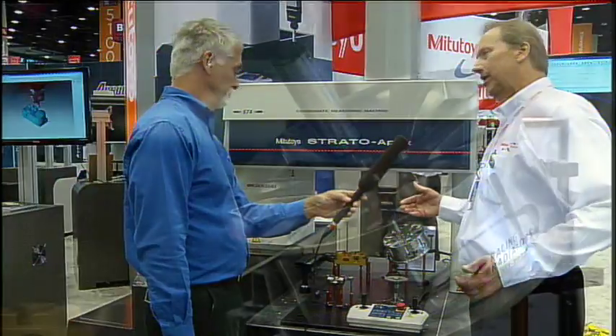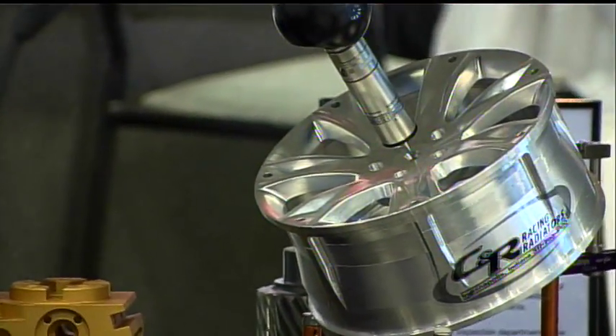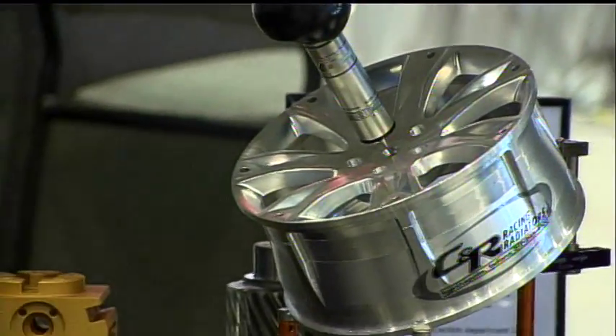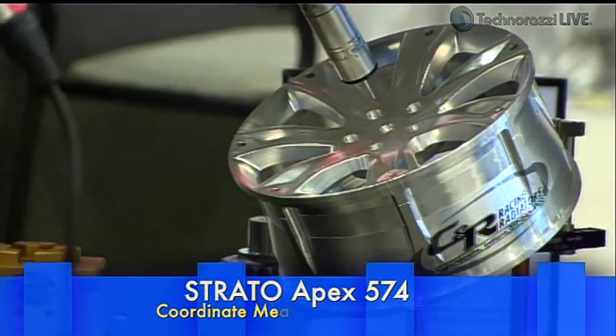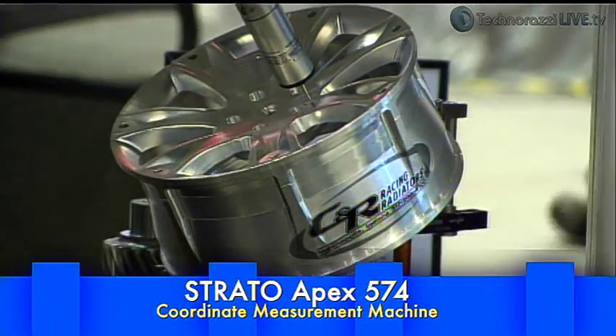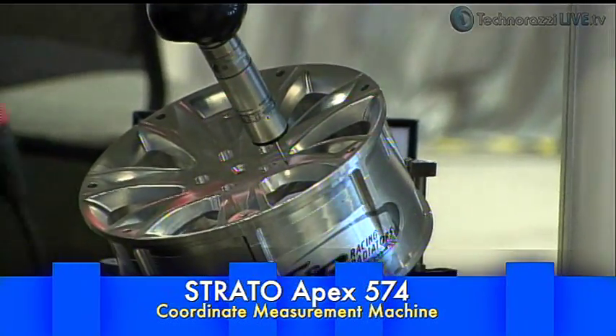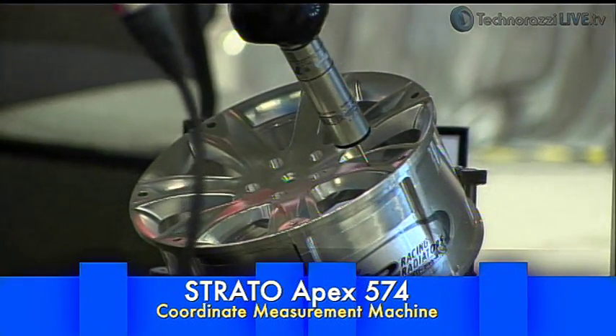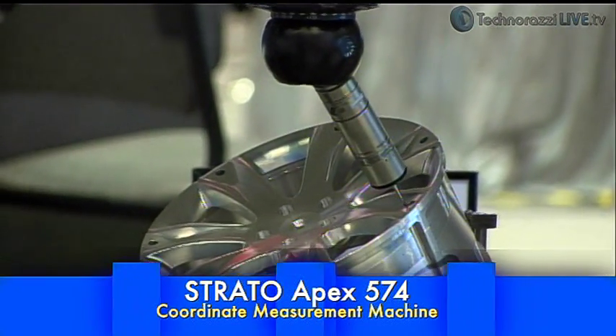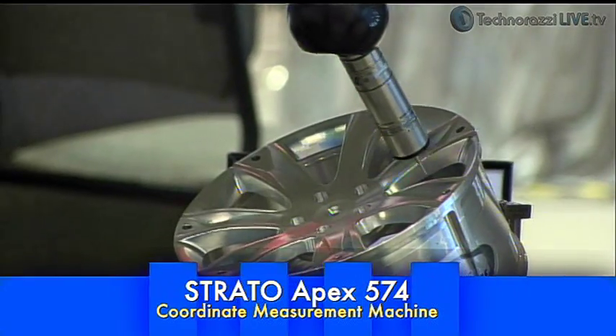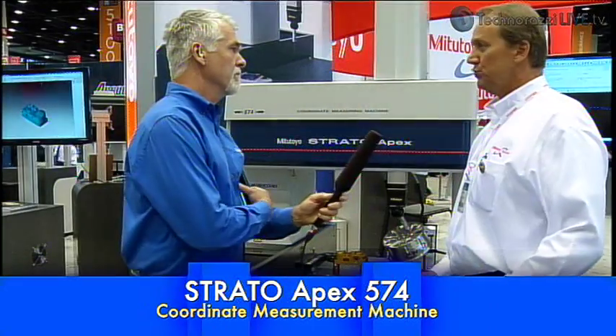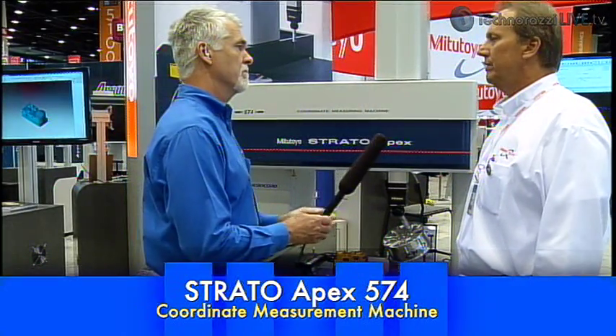This you would definitely see in a closed laboratory type environment. I'm still amazed at 0.7 microns. I mean, 700 nanometers. We're talking really small stuff. We're talking real small stuff, yes we are. And what was driving the need for that kind of accuracy? When we start getting into the 10th measurements, as far as perpendicularity, hole distances, true positions, you are going to want to produce a 10% of that, which brings us down into those types of measurements.